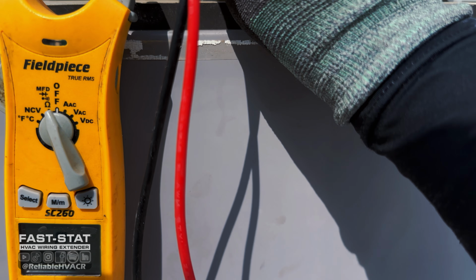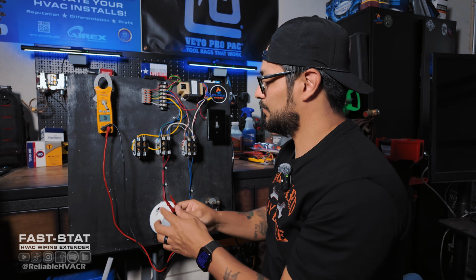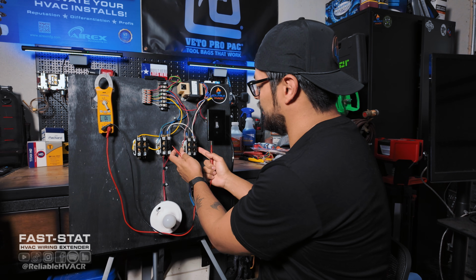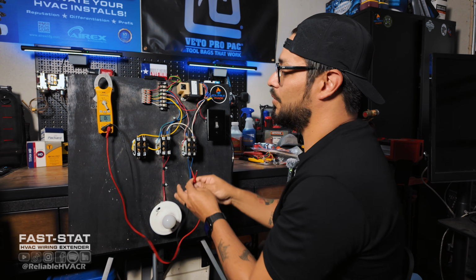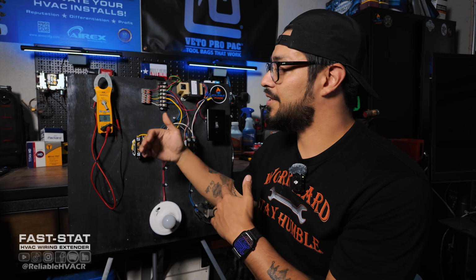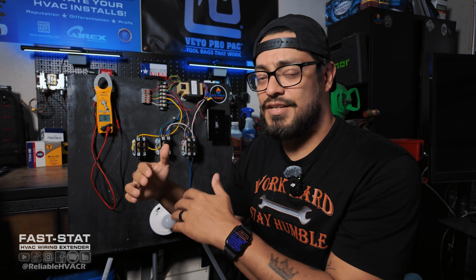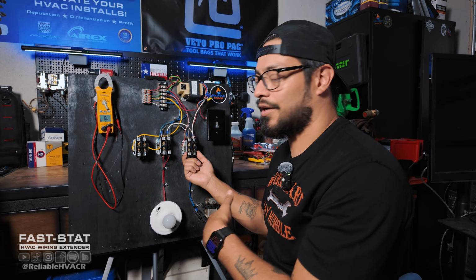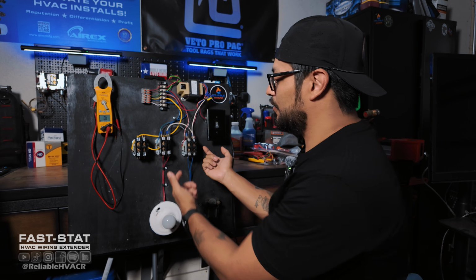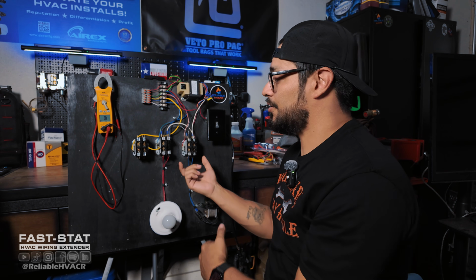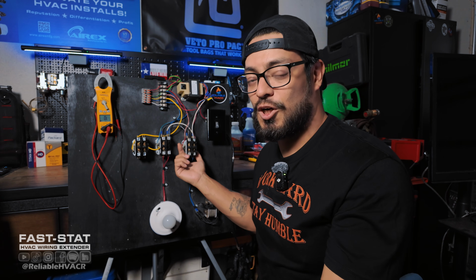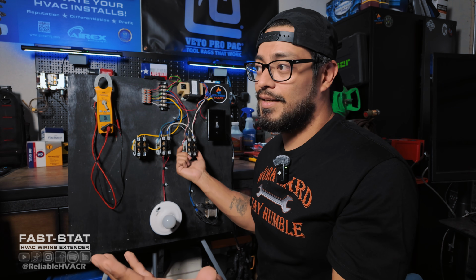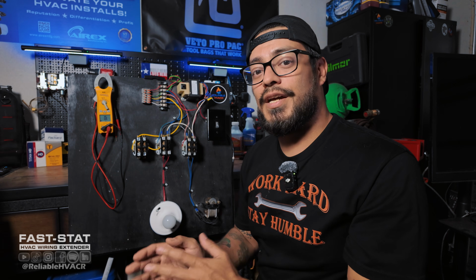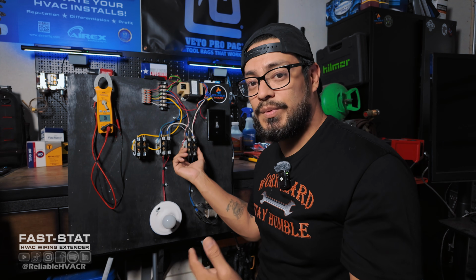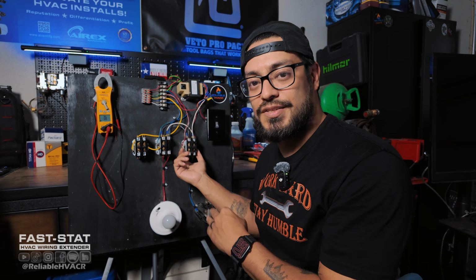So if you suspect that it's only tripping when the compressor calls or cooling calls, then you're going to go and disconnect your wires off the coil for that contactor, and you're going to start checking each one. Like I said, I've seen them as low as 7 or 8 ohms, but you need to get anywhere in that 10, 12, 13 range. I've seen some that go 16. Somebody mentioned that there's a formula, but basically the higher it is, whether like voltage, like if you guys are checking a 24 volt coil, it's going to be typically, I think, 10 to 12. If you're checking a higher one, because I deal with commercial equipment, sometimes that coil is 120 volts. Sometimes we have 3-pole, 208, 230. All that varies with that resistance on that coil. So typically I've seen a few different ones. As long as it's not 0 or 0 point something, I know we're good.